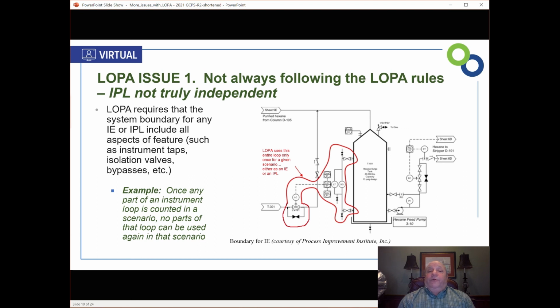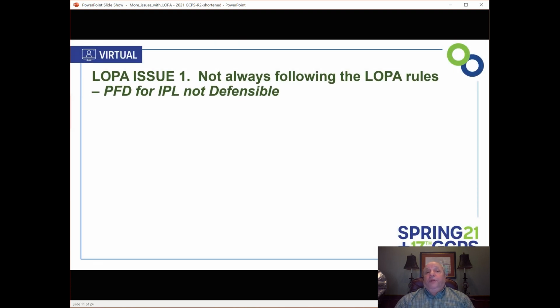So don't go with your knowledge or tables that only look at the level control valve failure or the level sensor failure. The whole loop's failure is what we consider, and that's many ORs, many types of failures. So that's another reason we draw the boundaries, and it's good for you to get used to drawing such boundaries in your own LOPA.